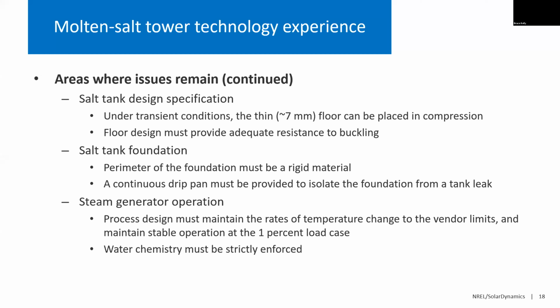Also, this expanded clay is a ceramic material, which is chemically inert, except that it can go from one oxide state to another when exposed to salt. And as a byproduct of that, the salt will decompose and form NOx in the form of a gas. And this happened at Crescent Dunes. It's actually quite a dangerous situation, and a few people were hurt at the plant due to NOx production coming from the foundation. So ideally, you'd like to make sure that you wouldn't repeat that situation. And if there's a leak in a future tank, you'd like to make sure that salt doesn't come in contact with the foundation material for whatever reason.